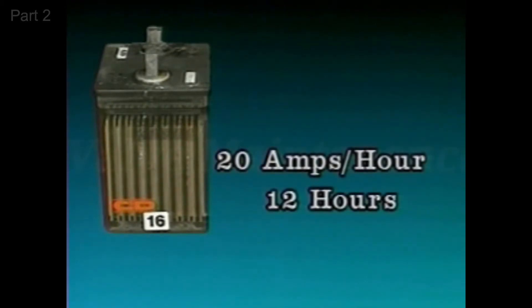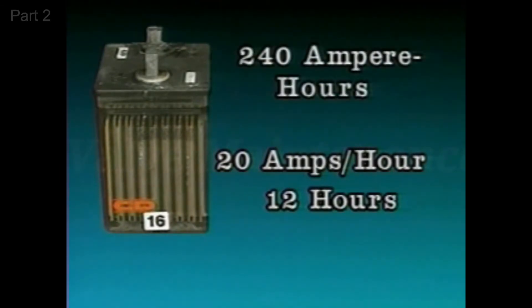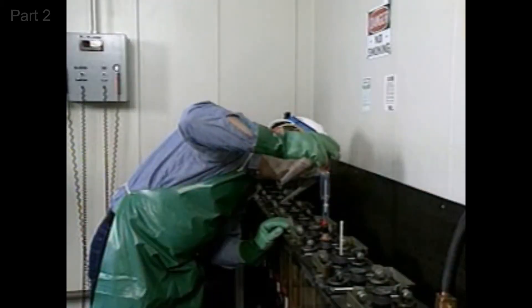On the other hand, if the load demands 20 amps, the cell can provide this current for 12 hours. This represents an ampere hour rating of 240. So the cell capacity is higher at lower discharge currents.